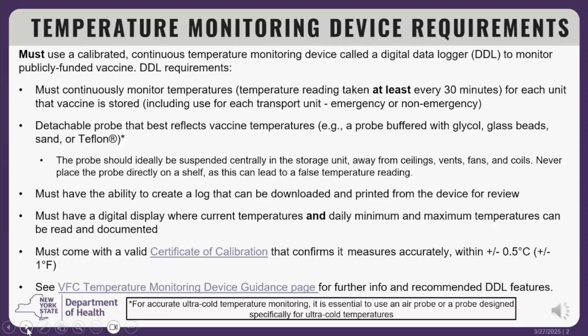The display is required to indicate the current temperature inside of the storage unit and also display the daily minimum and maximum temperatures reached. The device must come with a valid certificate of calibration that confirms it's measuring temperatures accurately. The device must measure temperatures within plus or minus 0.5 degrees Celsius or plus or minus 1 degree Fahrenheit. The DDL must have an audible high-low alarm for out-of-range temperatures, otherwise known as temperature excursions, and a low battery indicator to make you aware in advance that the device needs a change of battery.